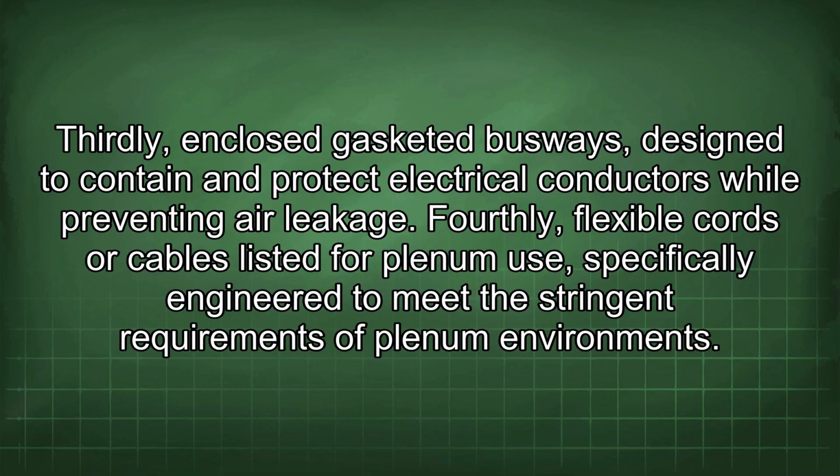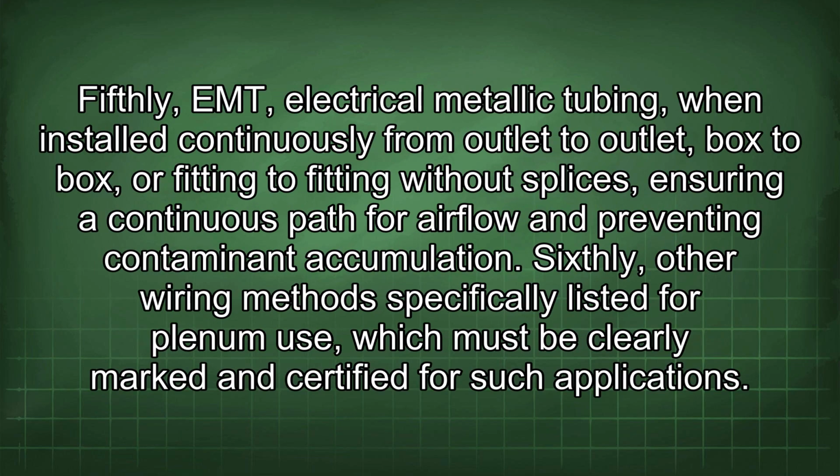Fourthly, flexible cords or cables listed for plenum use, specifically engineered to meet the stringent requirements of the plenum environment. Fifthly, EMT, electrical metallic tubing, when installed continuously from outlet to outlet, box to box, or fitting to fitting without splices, ensuring a continuous path for airflow and preventing contaminant accumulation. Sixthly, other wiring methods specifically listed for plenum use, which must be clearly marked and certified for such applications.